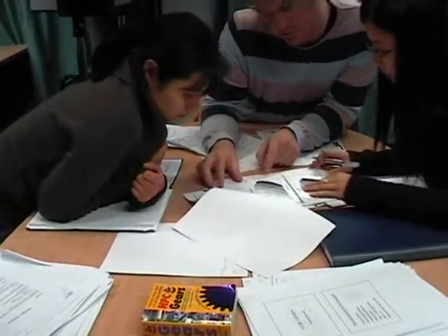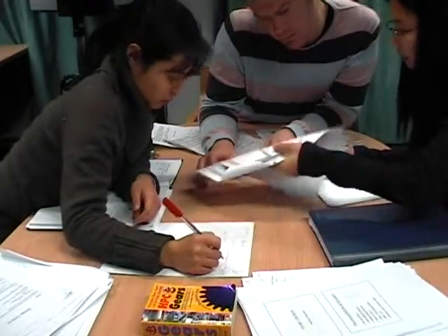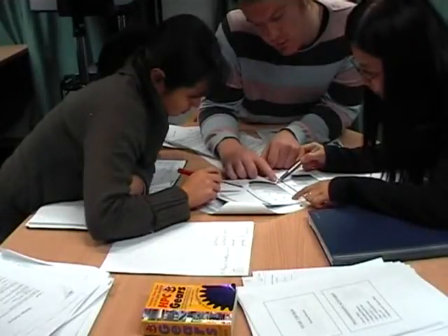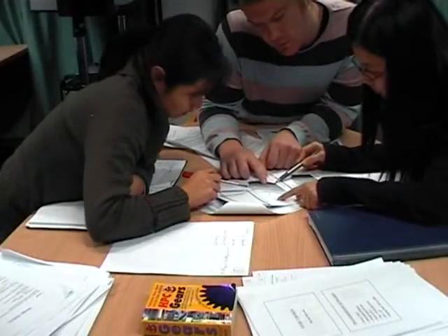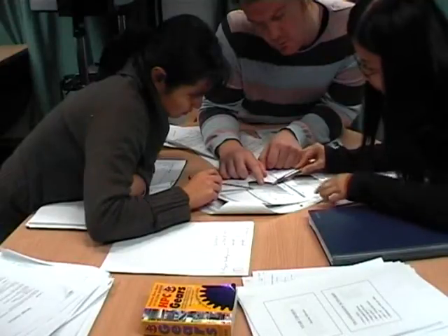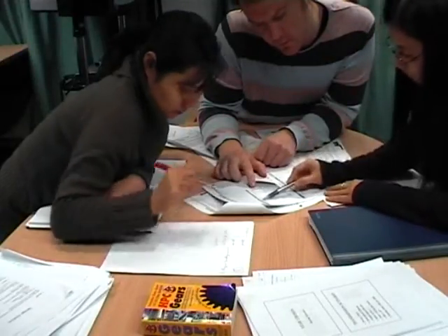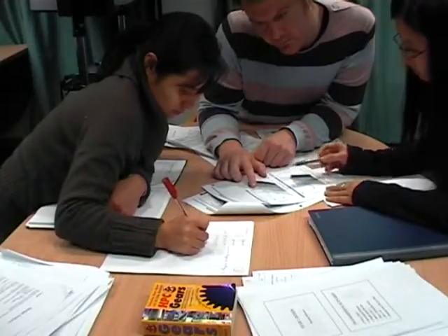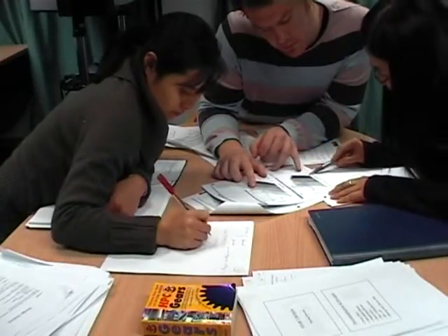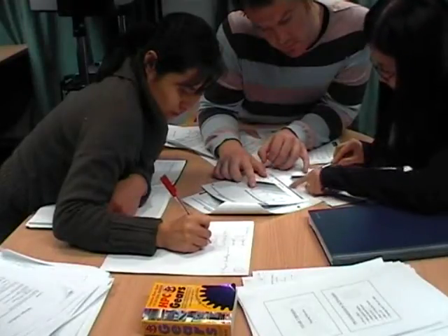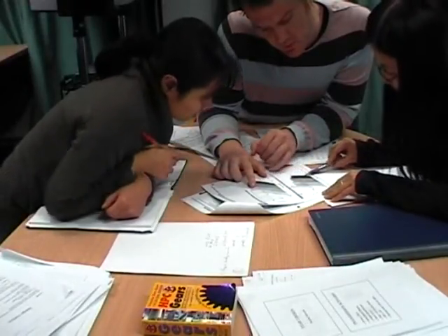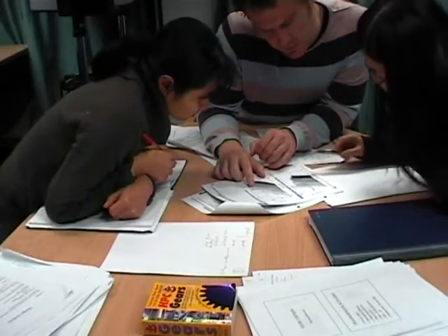What's the next page? Okay, there's HTD. Page HTD, 22.5 kilowatts at 1,500. So we're on 8M for the HTD, the HTD 8M range. And this one here is classical timing belt. I'm not sure. It looks to be on the border.